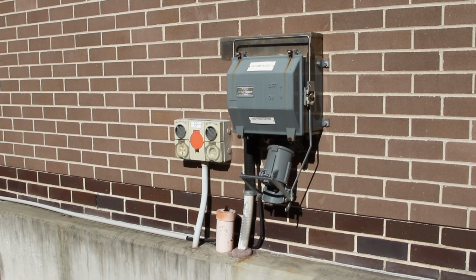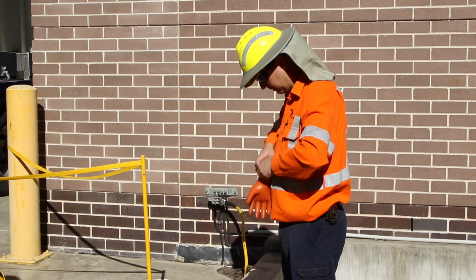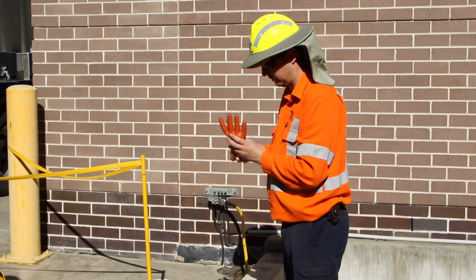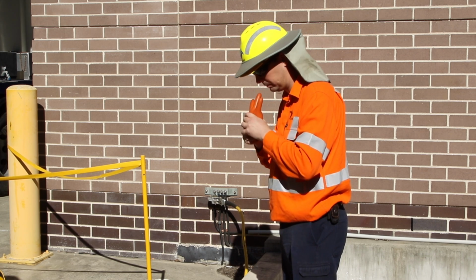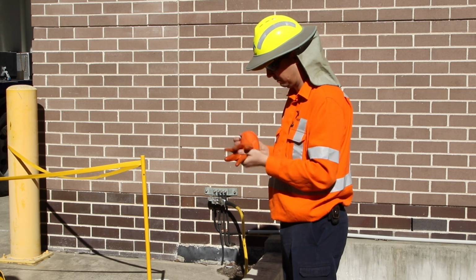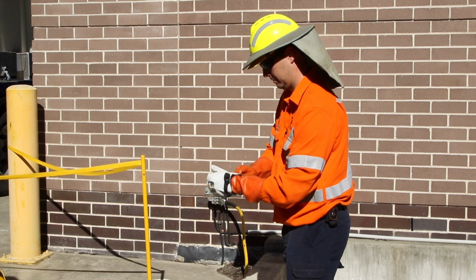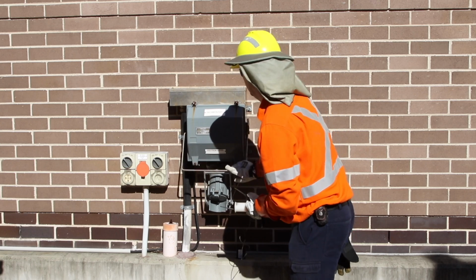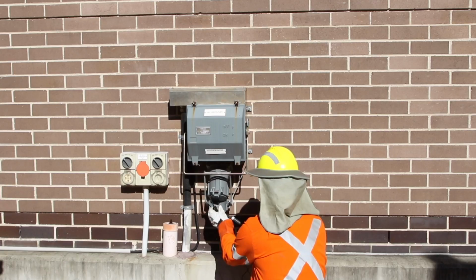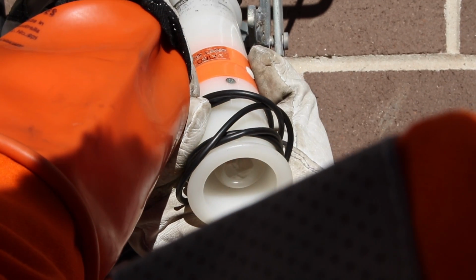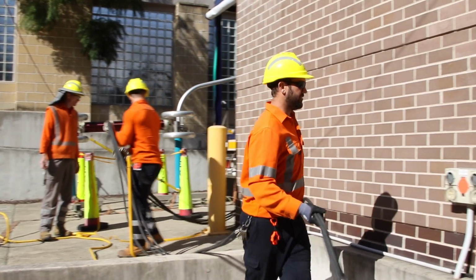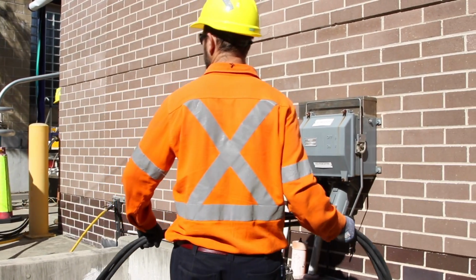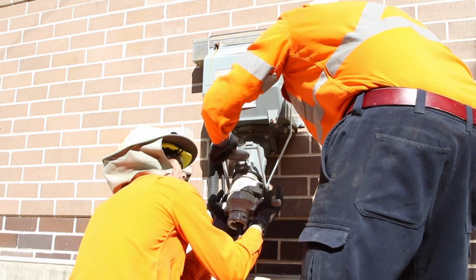Next, the test trailer is powered. The test trailer requires a 3-phase 100 amp power supply to run. The lamping procedure is used to check that the power socket has 3-phase supply and neutral present before it is used to power the test trailer. There are operational and safety concerns that prevent running the test trailer without proper supply.